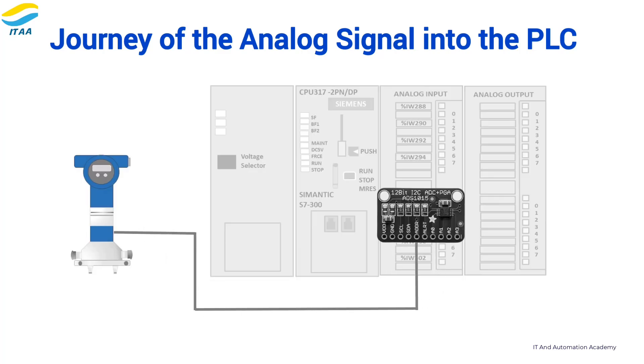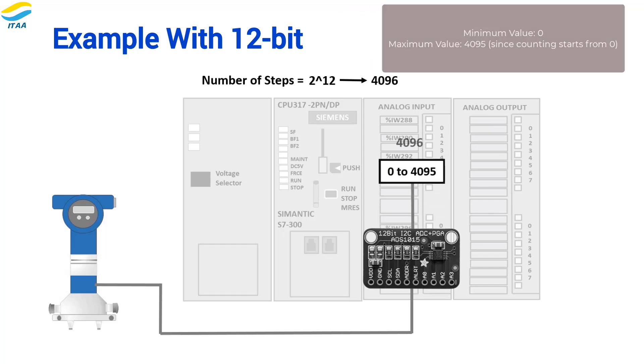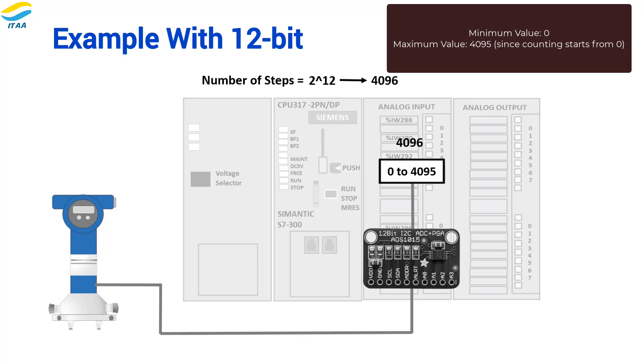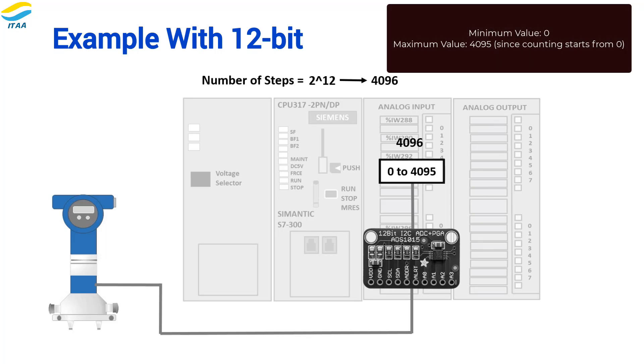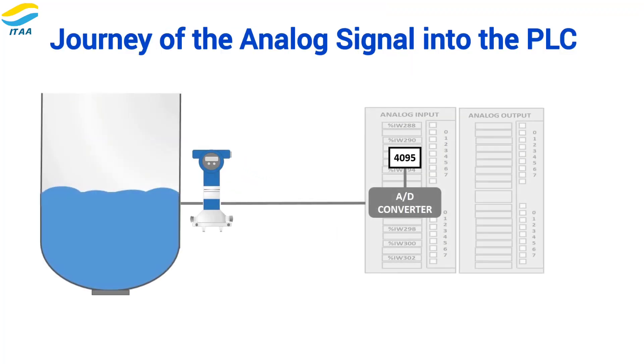For example, in a 12-bit resolution PLC, this raw value might range from 0 to 4095 counts. 12-bit resolution means the system can measure 2 to the power of 12 different steps, which is 4096 steps. So a 12-bit system can measure a signal in 4096 different values — minimum value 0, maximum value 4095, since counting starts from 0. As the tank level changes, this raw count changes accordingly.